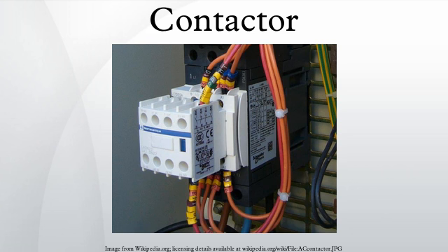Rapid start-stop. Relays and auxiliary contact blocks are rated according to IEC 60947-5-1: AC15, control of electromagnetic loads; DC13, control of electromagnets. NEMA. NEMA contactors for low-voltage motors are rated according to NEMA size, which gives a maximum continuous current rating and a rating by horsepower for attached induction motors.